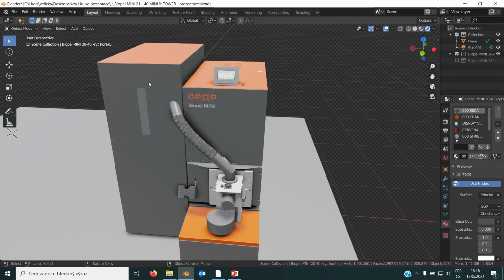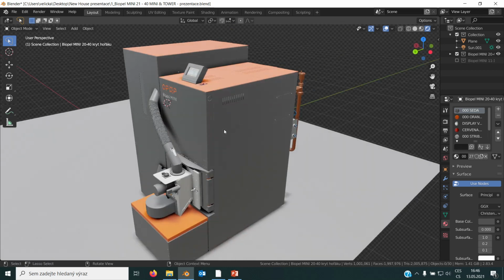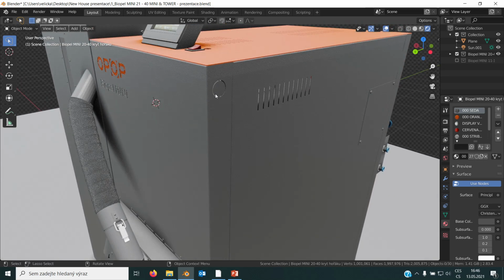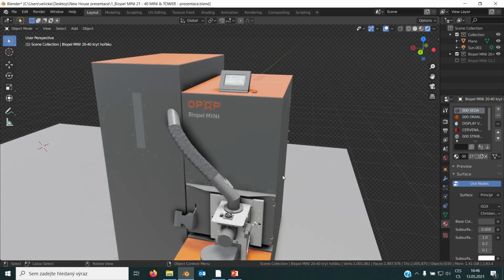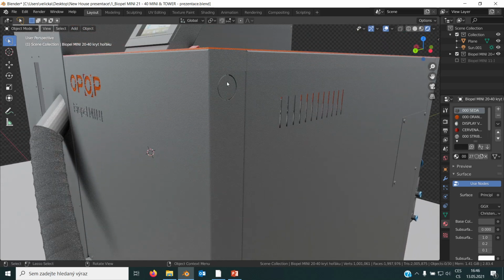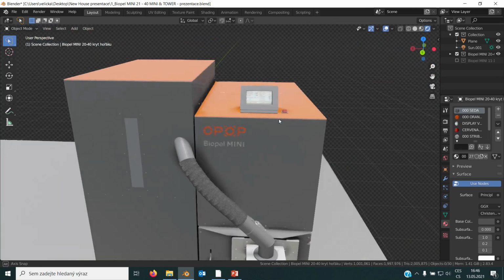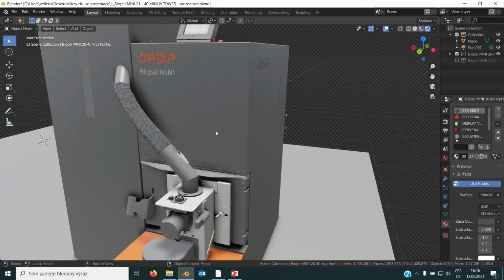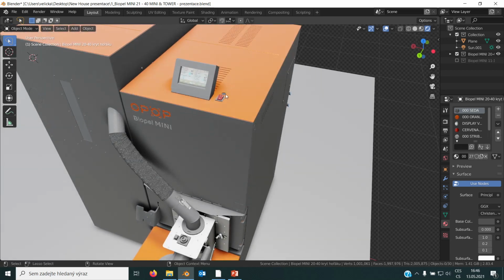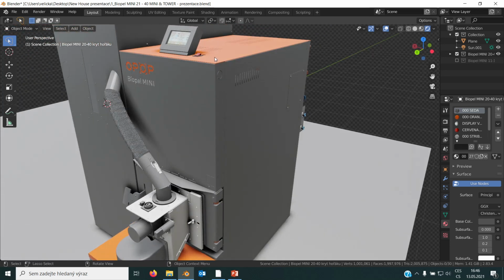Again, if the pellet hopper will stand on the right side, there is again an opening here protected by a small cover. So you just remove this cover, position the pellet hopper on the right side, and move the cable for the feeder to the hopper through this small opening, which is prepared for you on both sides, so you will choose. And speaking of the cable for the burner, again the cable is hidden here, and the cable goes behind the front cover to the bottom, and then it's connected to the burner.